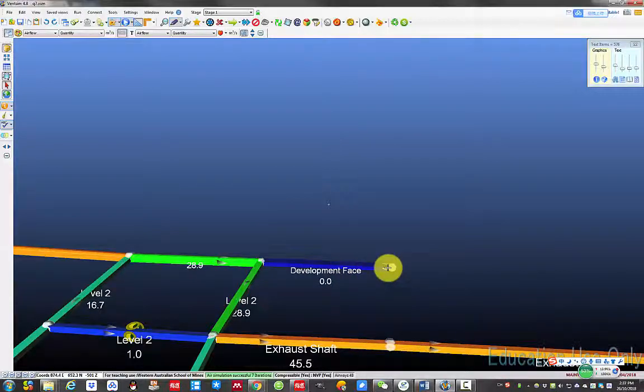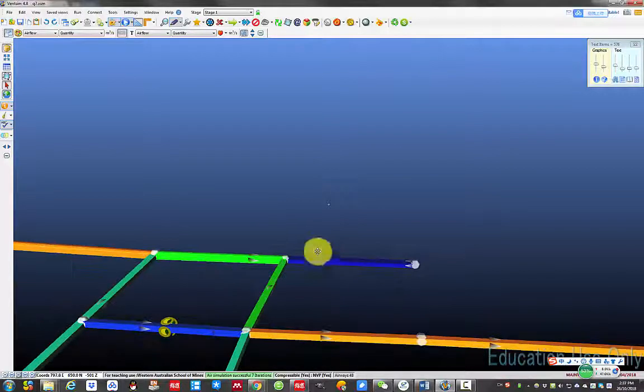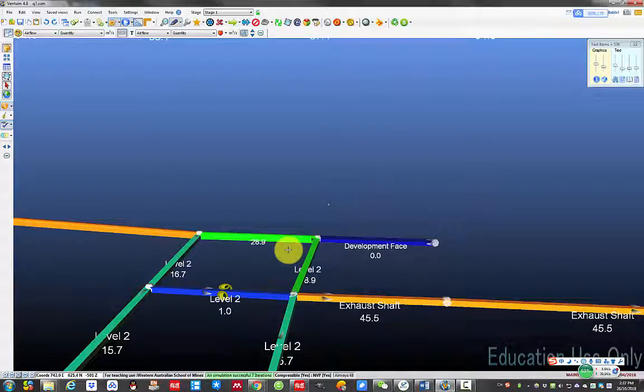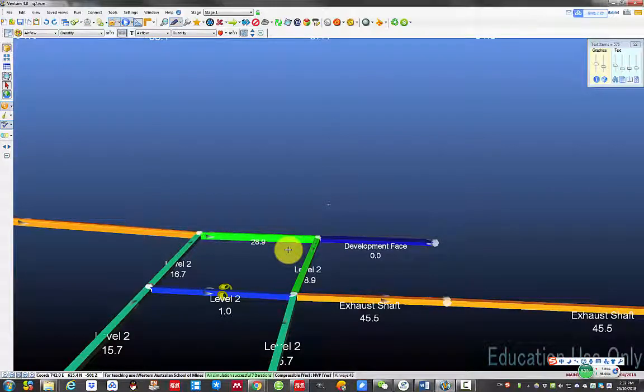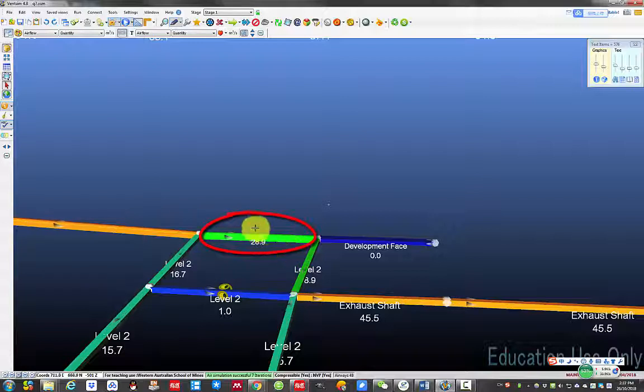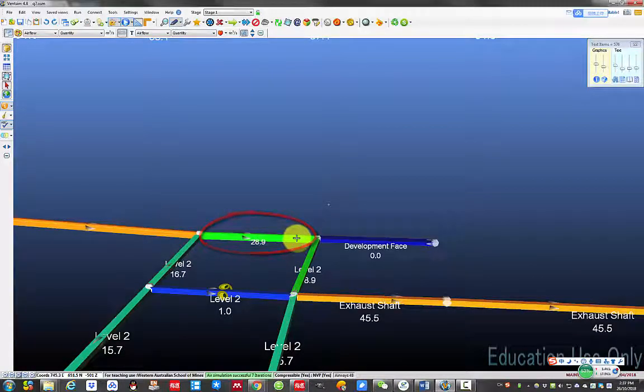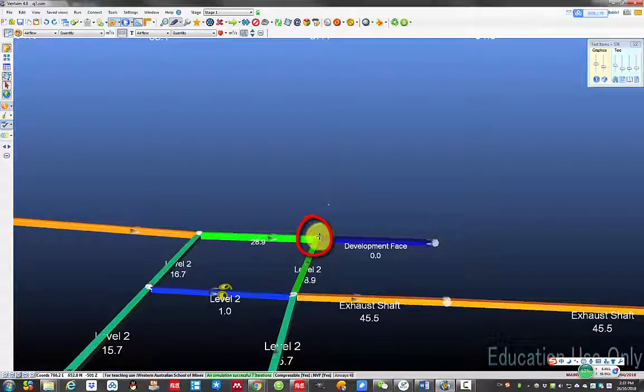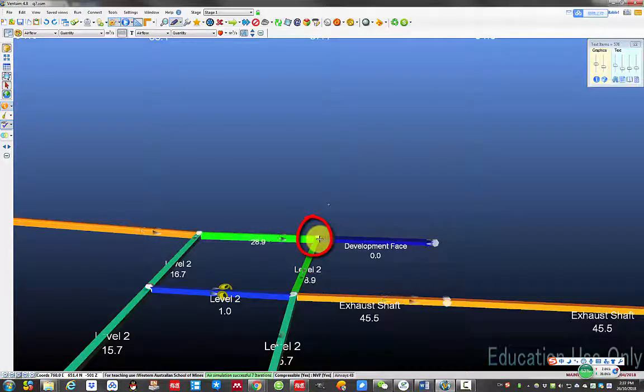We will build the duct first. In the metal mine, the most commonly used auxiliary ventilation is a forcing ventilation duct. The fan is located in upstream fresh air some distance away from the intersection point here to prevent air recirculation.